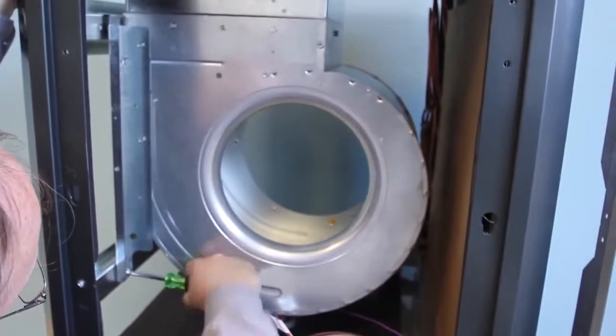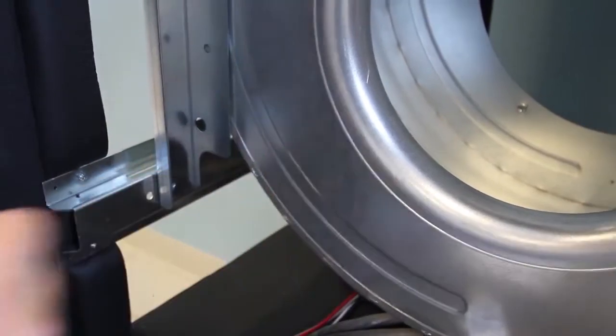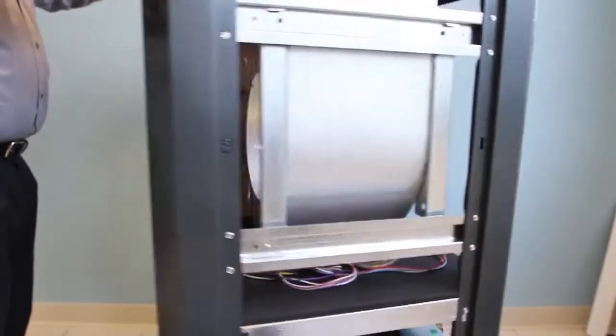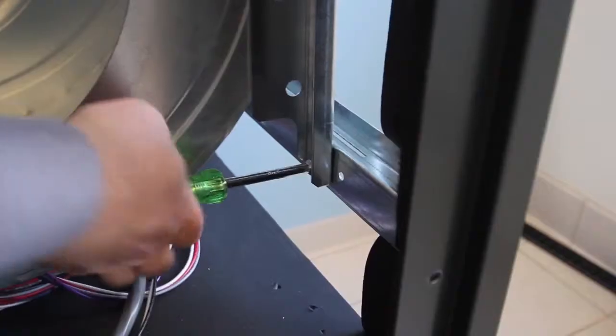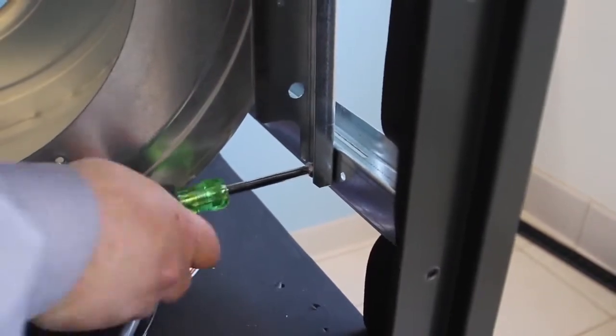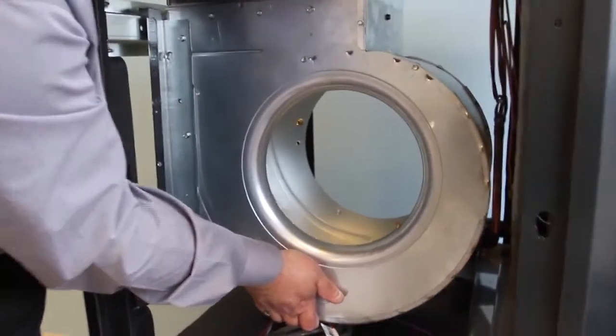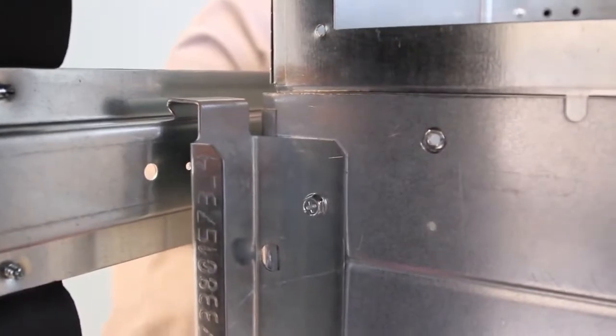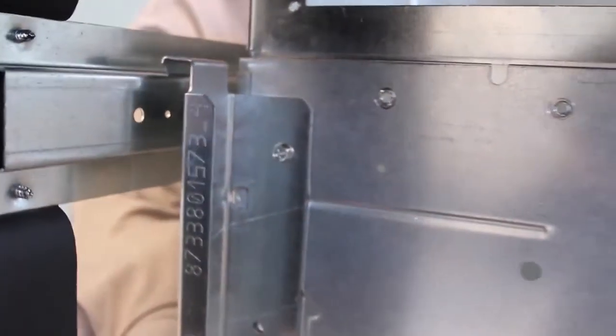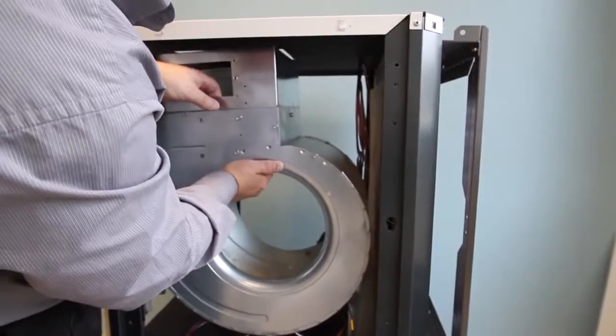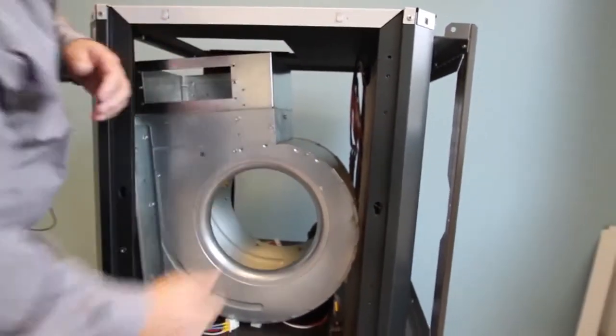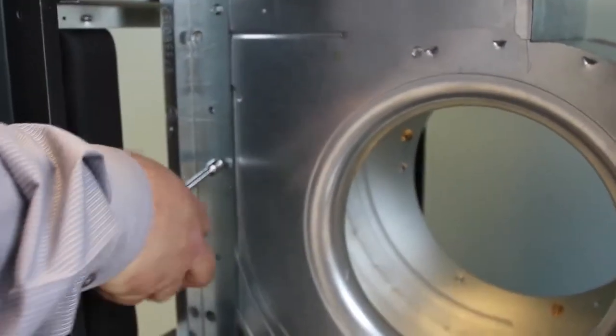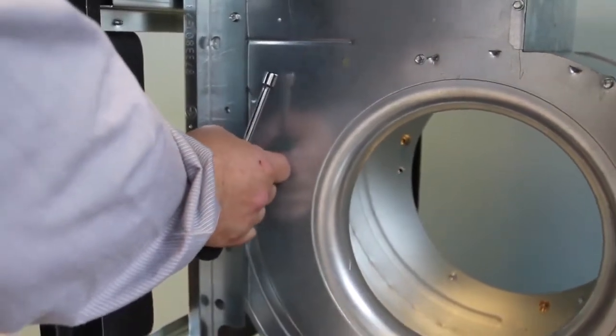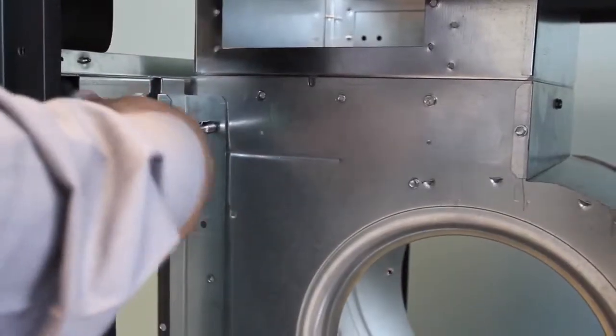Next, remove the screws on both sides of the blower, securing the vertical blower bracket to the horizontal support. Then you should be able to remove and retain the blower assembly by lifting up. Remove and retain the vertical brackets from the blower by removing the 4 screws, 2 on each side of the blower.